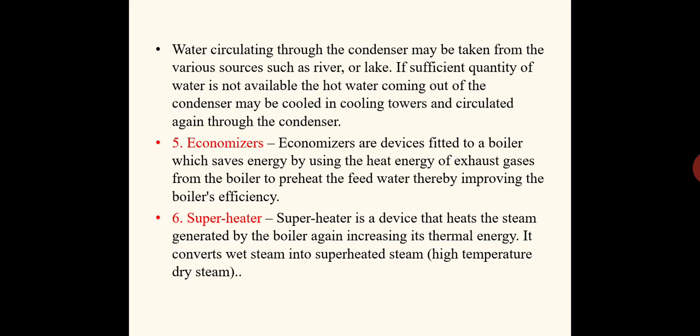So, that means this delta T value we can reduce. Inversely, what we are doing is reducing the heat input to the boiler. If the water coming to the boiler is preheated, we can reduce the heat input. Correspondingly, the consumption of the coal will also be less. That is saving of energy, so the efficiency of the boiler will increase.